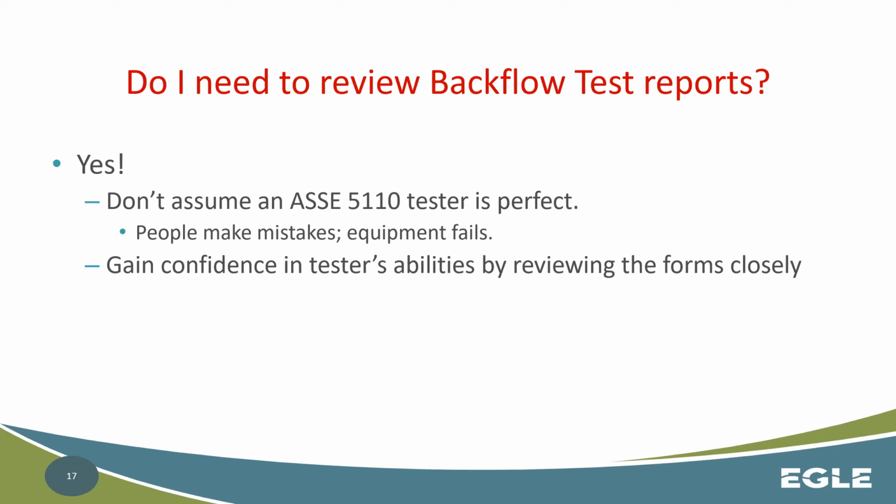And another thing you should do upon reviewing the records and maintaining them, you should go out and check that paperwork against the tag that is put on by that tester. If they're not putting a tag on, then you shouldn't use that tester anymore. Just take a word of advice.